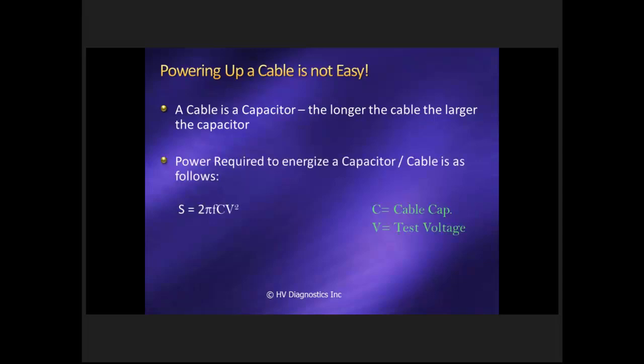The problem with power frequency is obviously energizing the cable. It is not easy to take a 110 volt power supply out of a wall or a small generator and energize the cable. The cable is electrically a large capacitor, and the longer that cable becomes, the more capacitance you have in parallel, and the bigger the capacitor becomes. The power required to energize that cable is given by that formula over there. You can see from the formula that power is very much dependent on frequency, the capacitance, and the voltage. The applied voltage, you can't really do anything about; you have to follow the standard. For the capacitance, you can start cutting the cable up in half or quarters, what's called the salami method, and that's not very popular with a lot of customers. The other alternative is to bring the frequency down to minimize your power requirements.